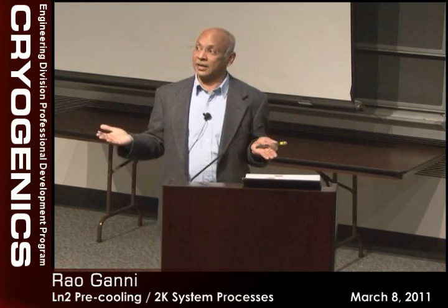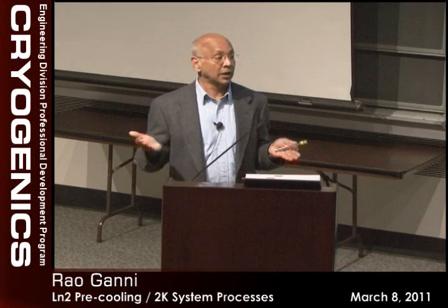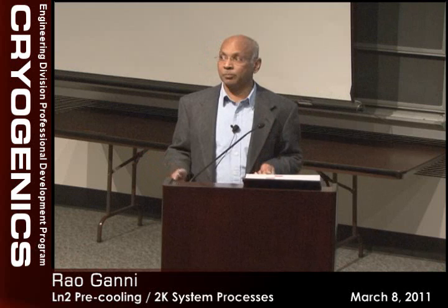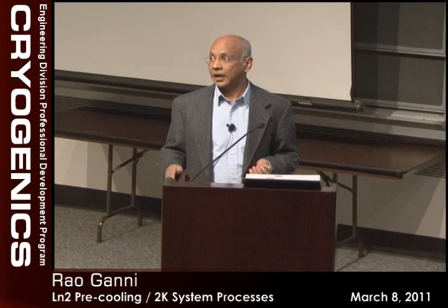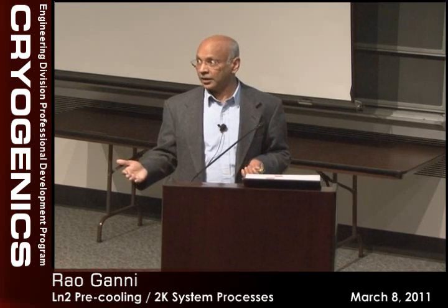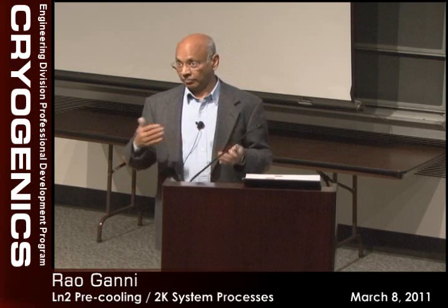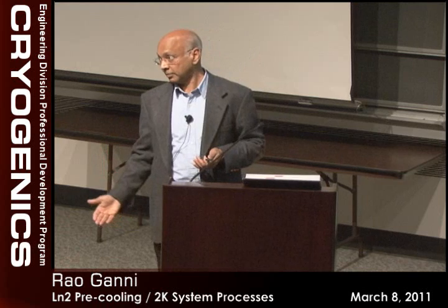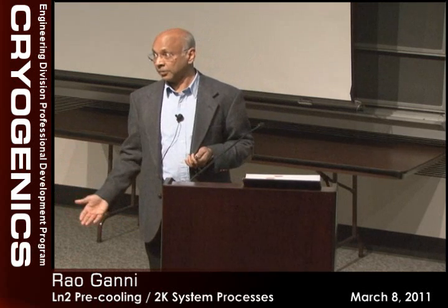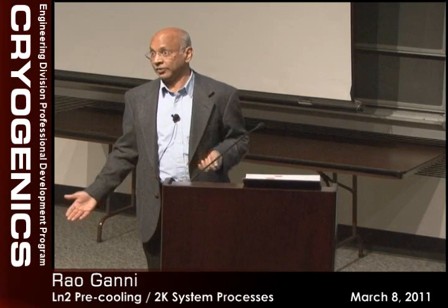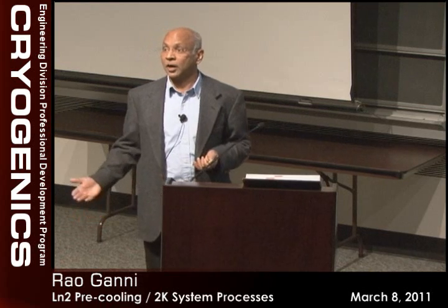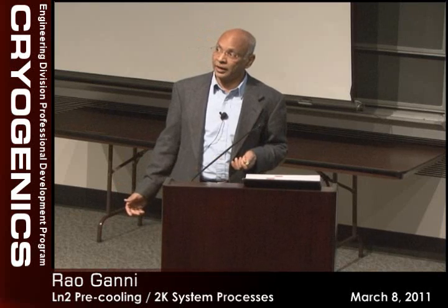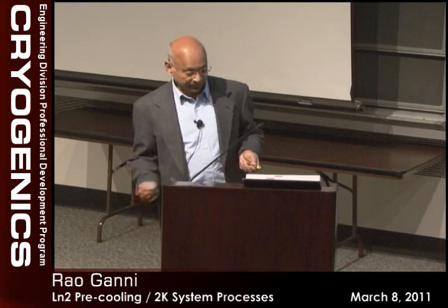So we try to balance, as the in-between at CHL, what exactly you need for the operating conditions, and what is the price, capacity balance, operating cost and the reliability. So that's what we do indirectly without bringing it to your attention. I mean, we could have run it at lower pressures at a reduced capacity, with increased operating cost and less reliability. But if it's not doing any more good than what you can do at a higher temperature, that's why we operate around 2.07 to 2.08 in our Linac.